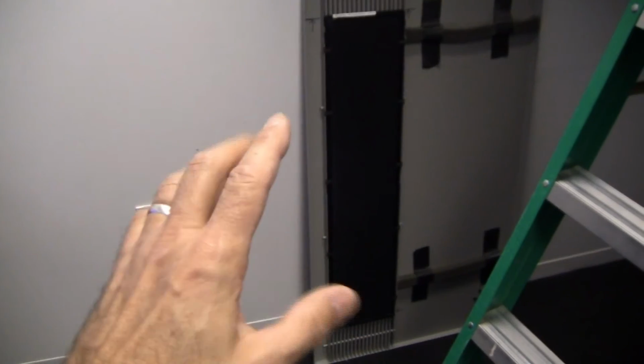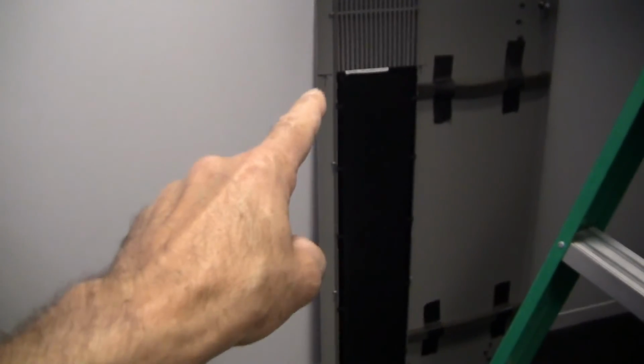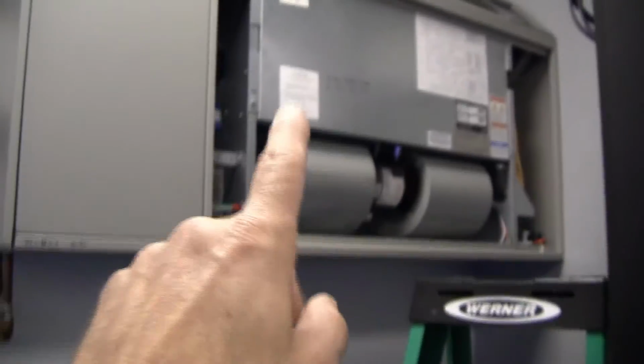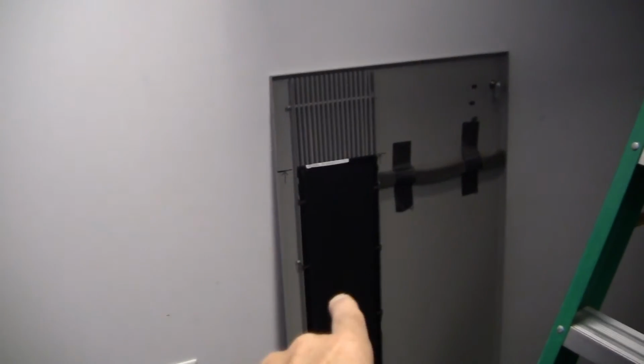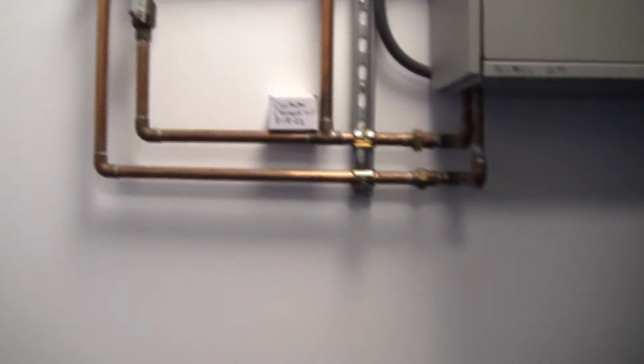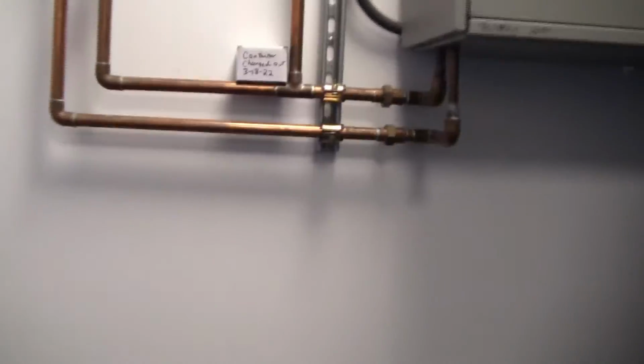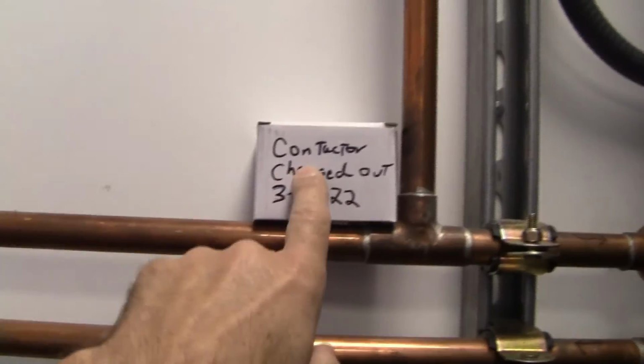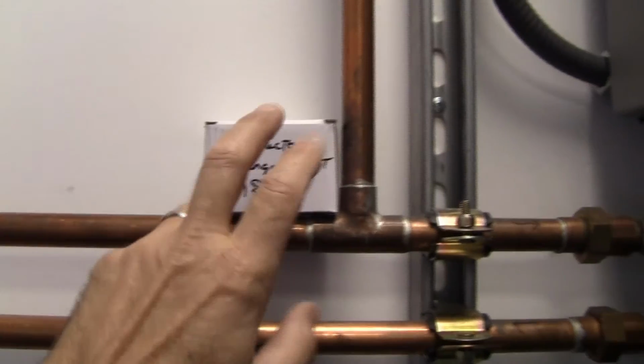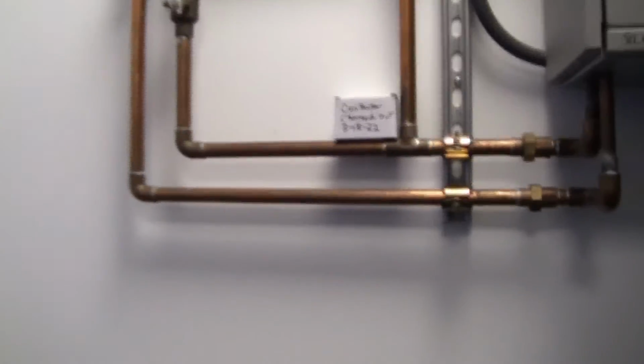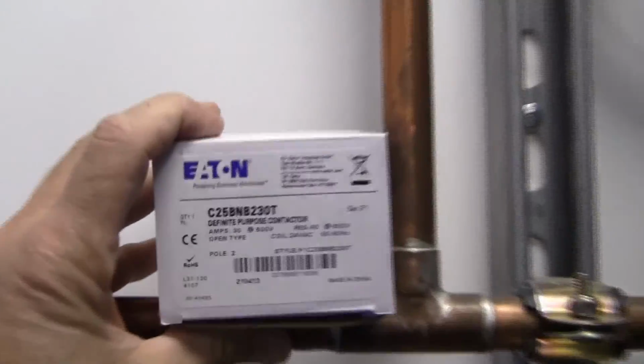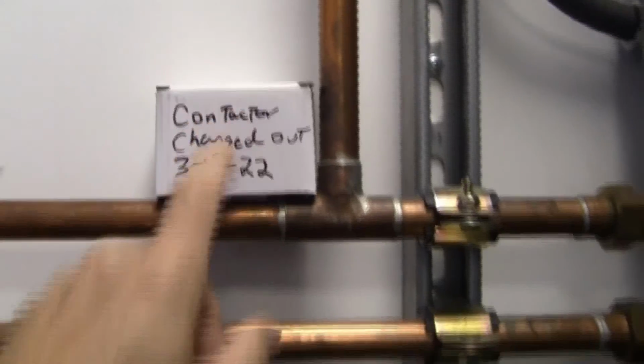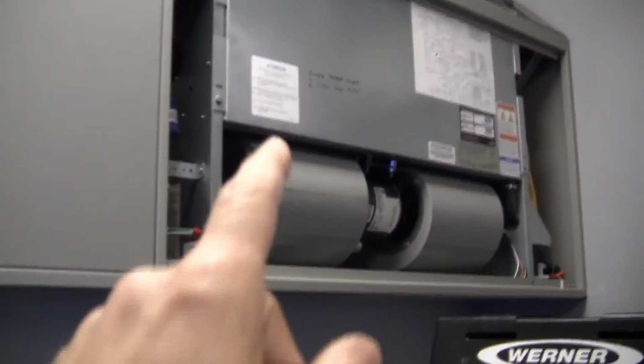I also want to mention that since I'm into the project, I took the air filter, which is right here. It goes on this panel door right here. I took that air filter off and took it to the kitchen sink and just washed it out so it's going back 100% brand new. And I put all the door skins on except for this one panel here that will go on last. I just took the contactor and left it here at the job site. Contactor changed out, put the date on it right there if anyone wants to observe that old contactor. Plus it also has the model number of the new contactor that we just installed. So good information there, not really taking up any space. Button up the ceiling tile. All I have to do now is put that panel door on.